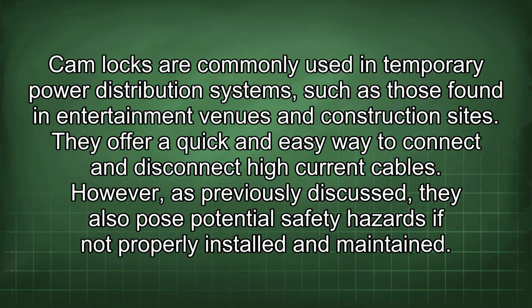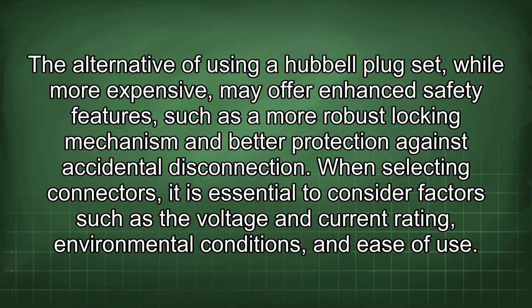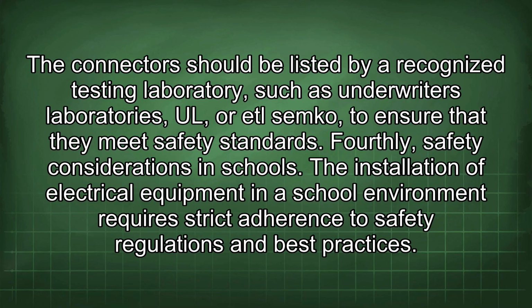However, as previously discussed, they also pose potential safety hazards if not properly installed and maintained. The alternative of using a Hubbell plug set, while more expensive, may offer enhanced safety features, such as a more robust locking mechanism and better protection against accidental disconnection. When selecting connectors, it is essential to consider factors such as the voltage and current rating, environmental conditions, and ease of use. The connectors should be listed by a recognized testing laboratory such as Underwriters Laboratories, or ETL SEMKO, to ensure that they meet safety standards.